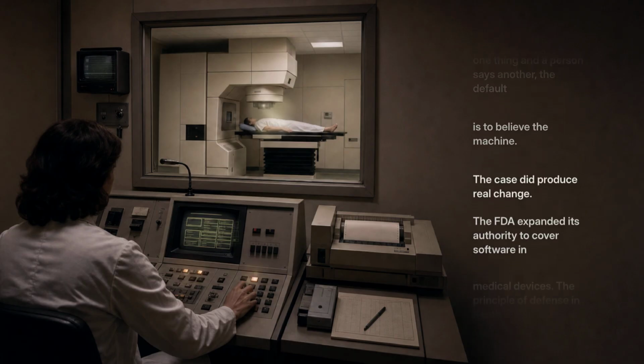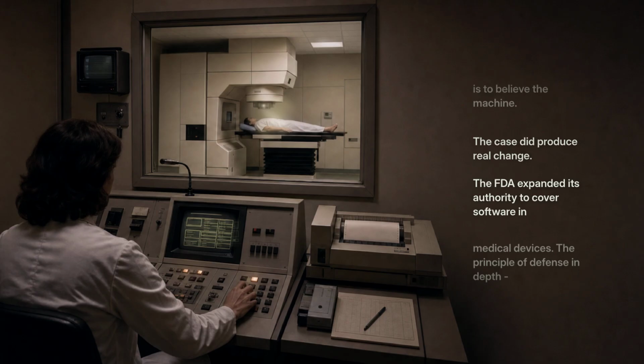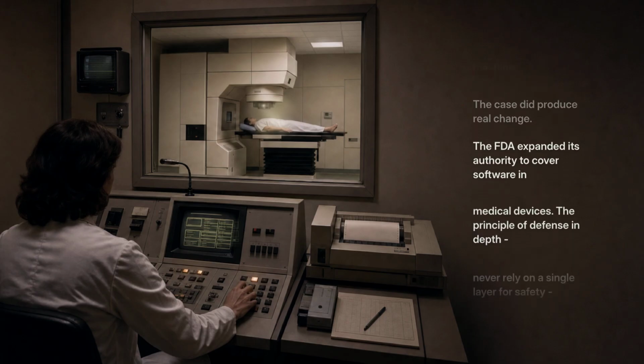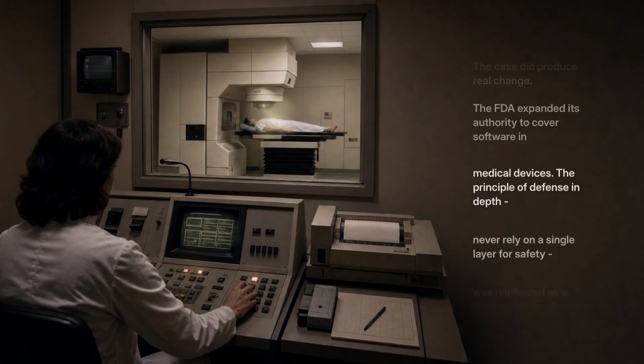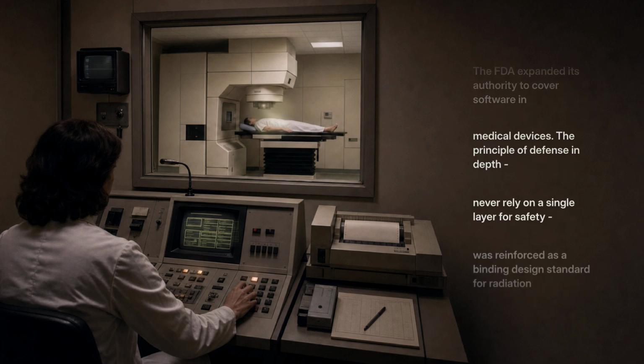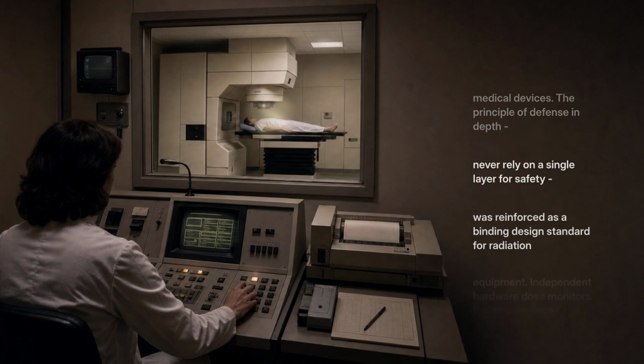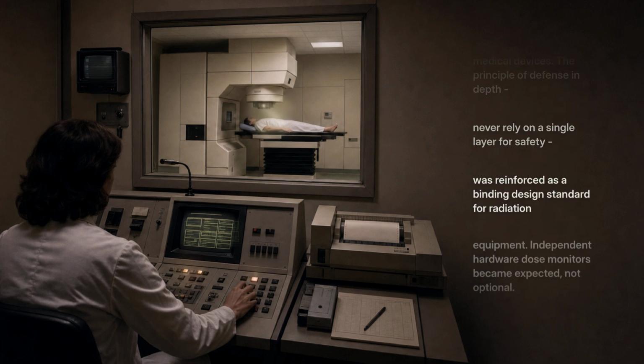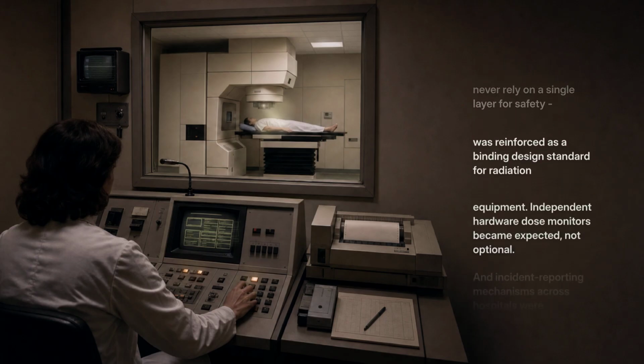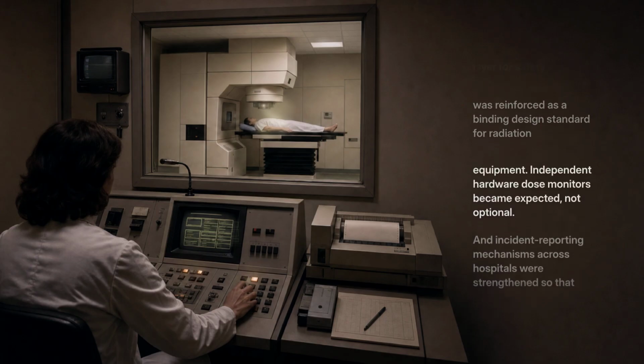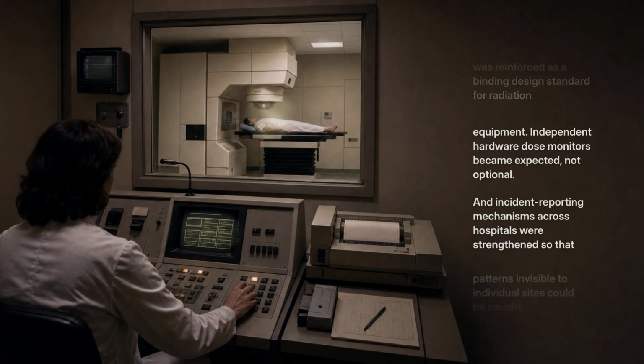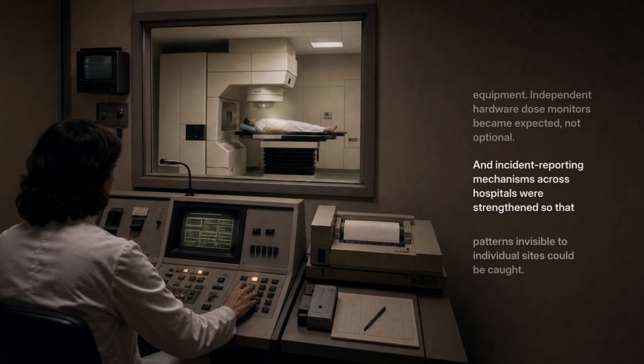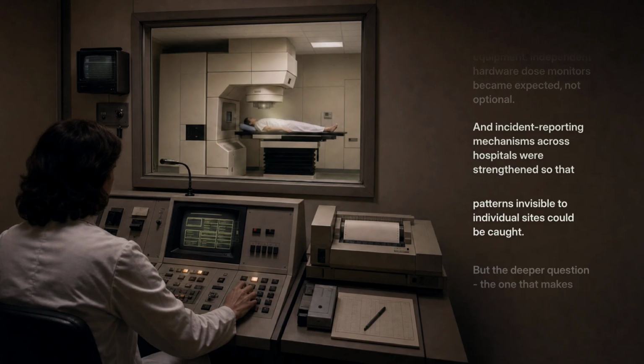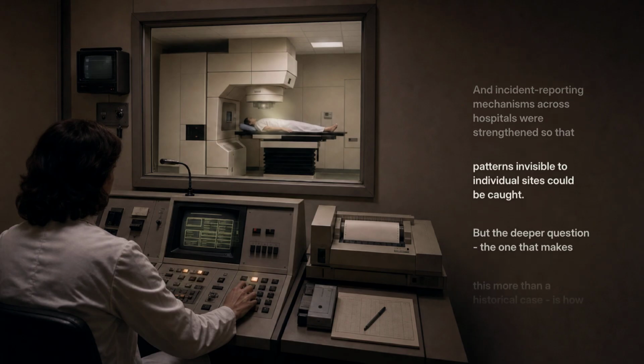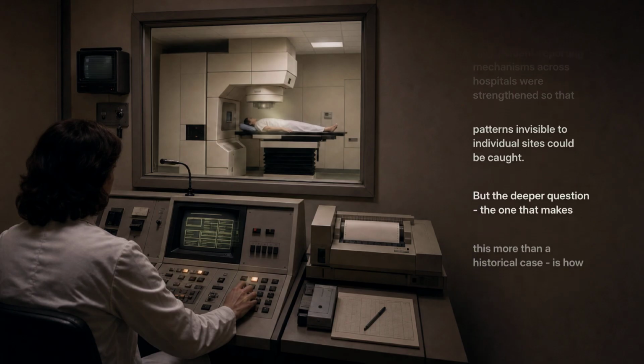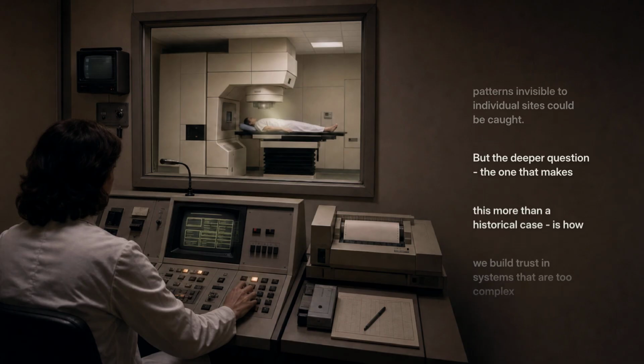The case did produce real change. The FDA expanded its authority to cover software in medical devices. The principle of defense in depth, never rely on a single layer for safety, was reinforced as a binding design standard for radiation equipment. Independent hardware dose monitors became expected, not optional. And incident reporting mechanisms across hospitals were strengthened so that patterns invisible to individual sites could be caught.